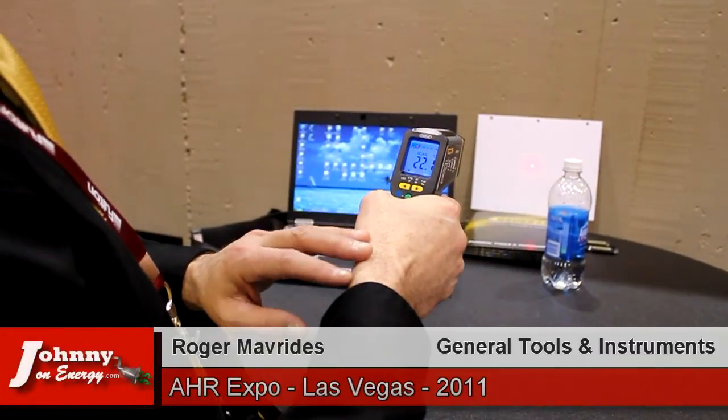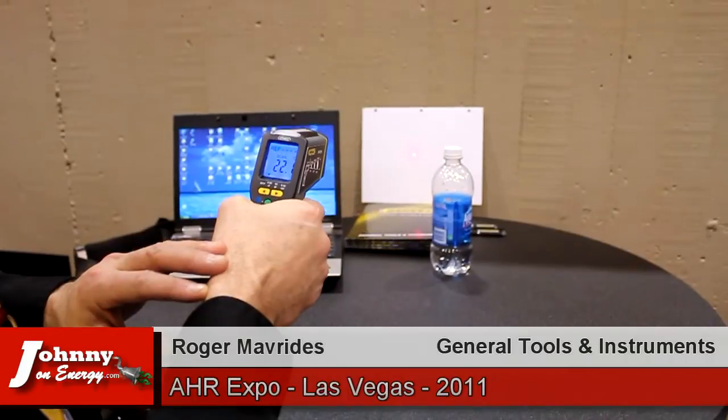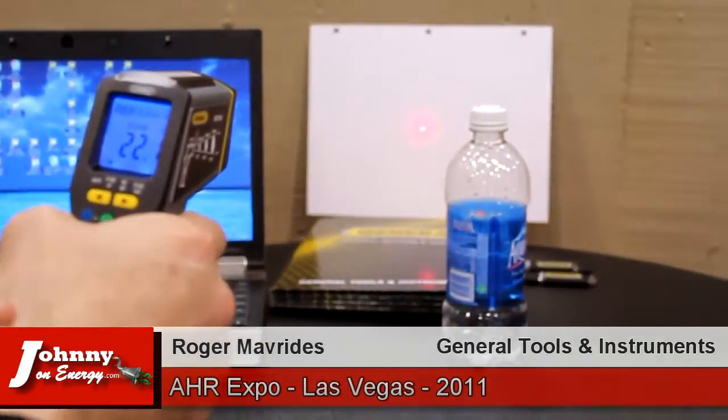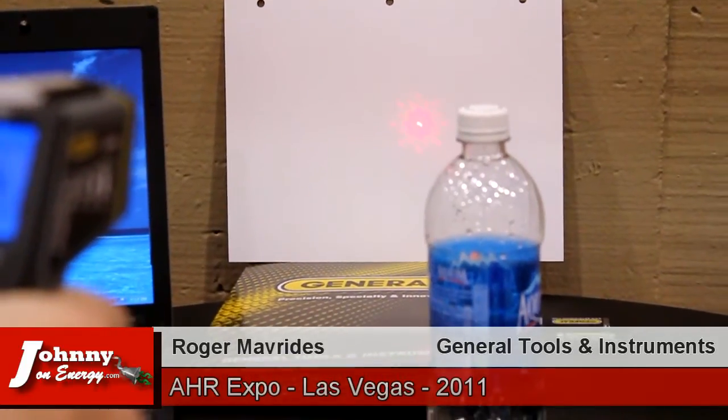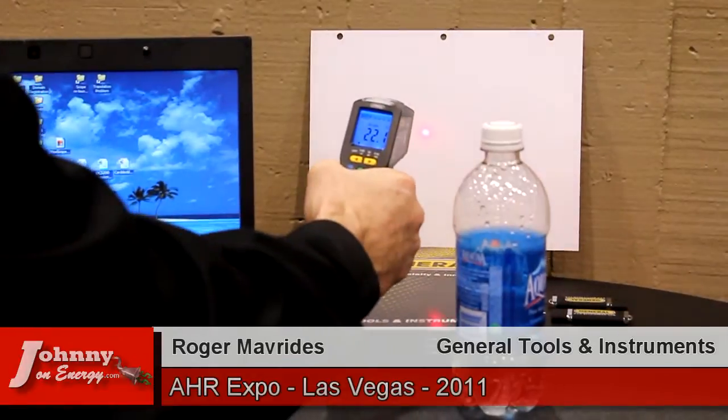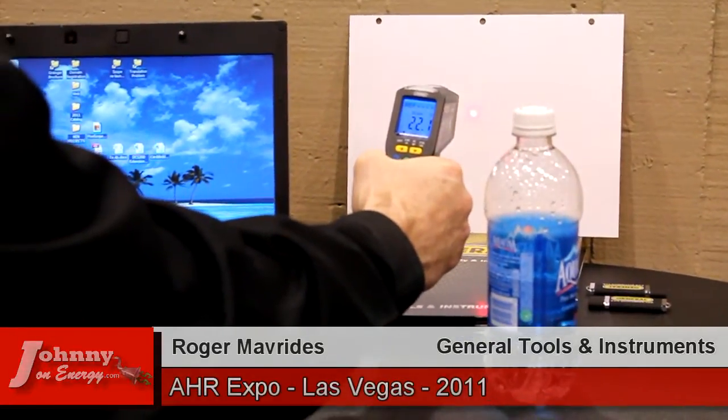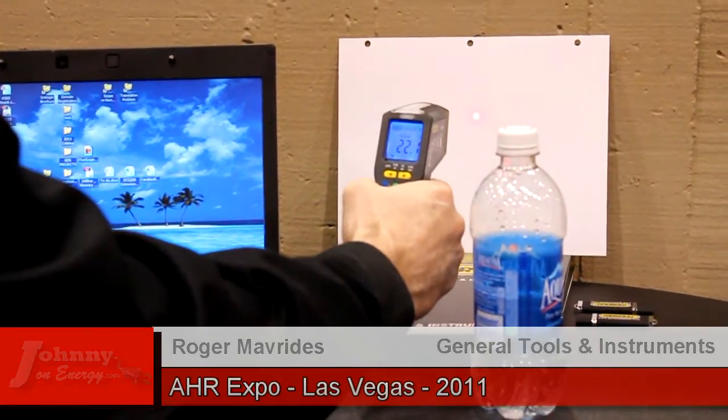One of the unique features of this instrument is its starburst laser pointer and what that does is it represents one half of the target spot size, the diameter. This is an 8 to 1 ratio which means that from 8 inches away the target spot normally is 1 inch. That laser dot is half an inch in diameter.